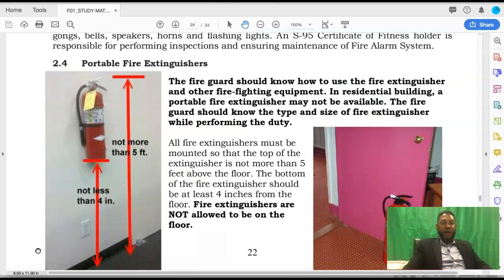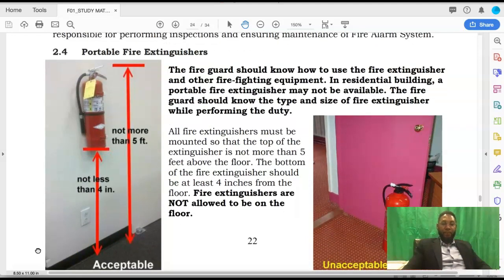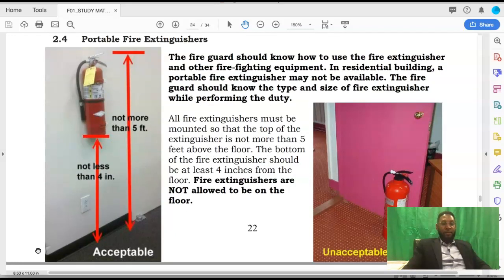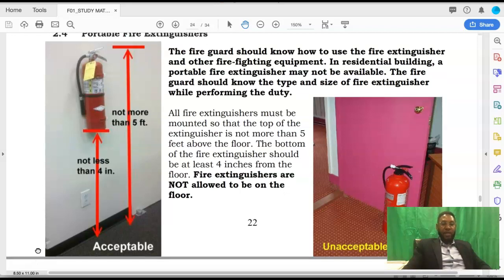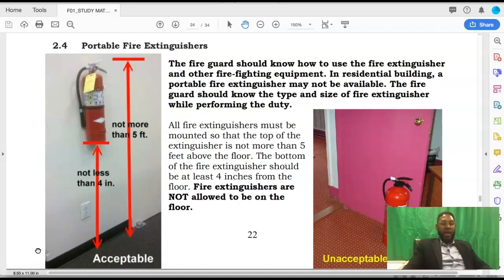So let's talk about the portable fire extinguishers here. If you look at the diagram here, you see that it is not more than 5 feet high and not less than 4 inches to the ground. And that is the prescribed way a fire extinguisher should be hung on the wall. A fire guard should know how to use a fire extinguisher and other firefighting equipment. In residential buildings, a portable fire extinguisher may not be available. The fire guard should know the type and size of fire extinguishers while performing his duties.